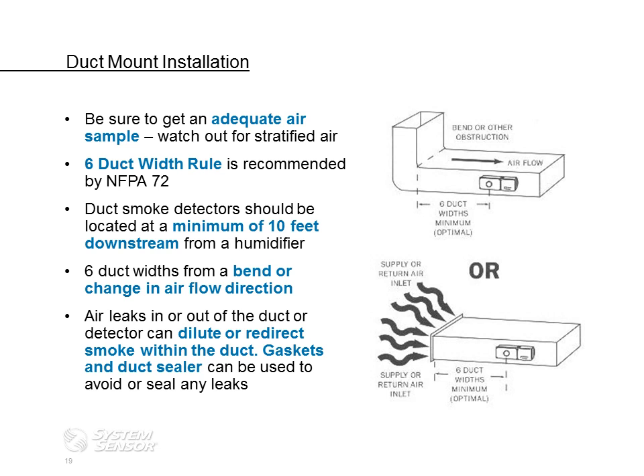Again, the 6 duct width from a bend or a change in airflow direction. And what we're really trying to do, and why you're seeing a common theme, is we're really trying to avoid turbulent air or stratified air. We want the smoothest, most consistent airflow that we can get out of the ductwork. It's also very important to make sure that you eliminate the air leaks in and out of the ductwork. We want to make sure that we have a good seal in the ductwork and around the duct detector so that we ensure we maintain that proper pressure differential so that the detector functions correctly.